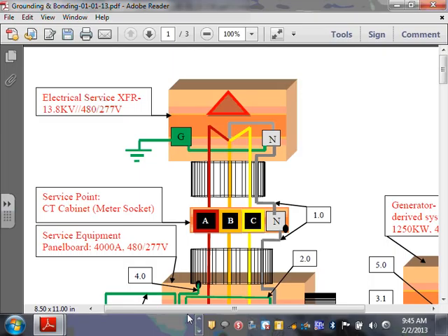Okay, and it's color-coded. This is supposed to be your brown, by the way, and this is your orange and yellow, and this is supposed to be the gray, right? Isn't that the typical, not code required, but typical industry standard for 480/277? I don't know if it looks like brown here, right? So I apologize to you guys. Yours look all like one mess of a color here. Okay, any comments, guys, about bringing the service to the building?